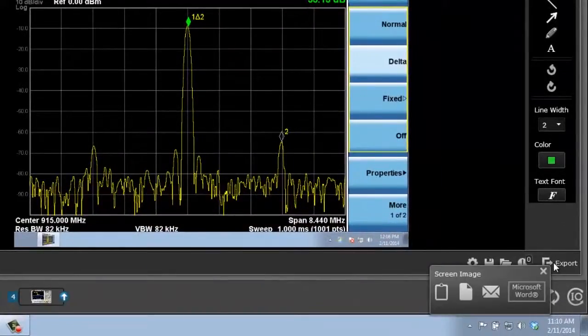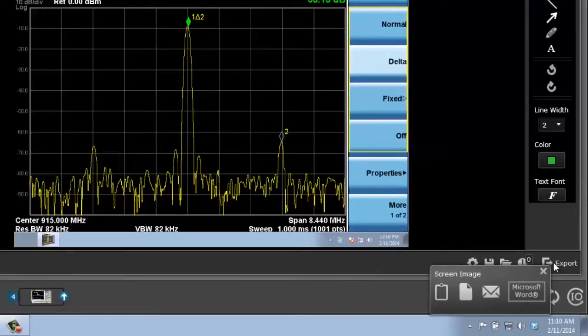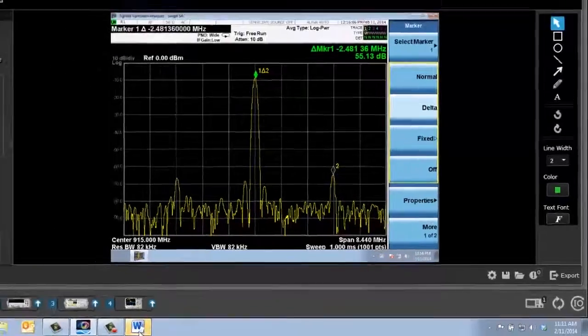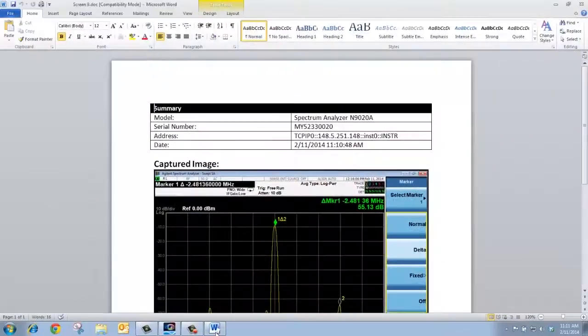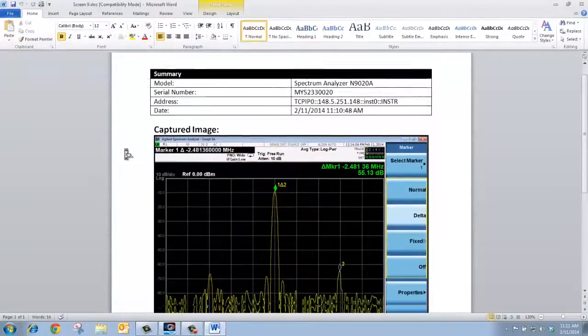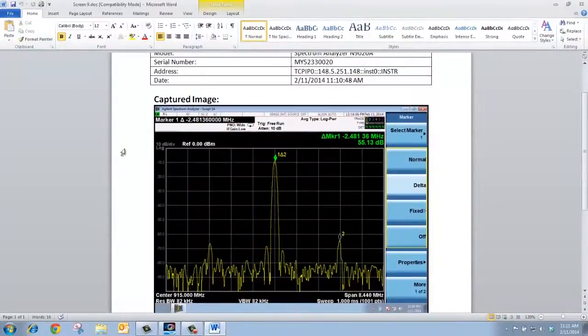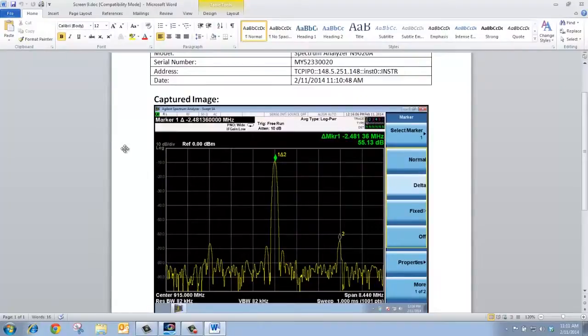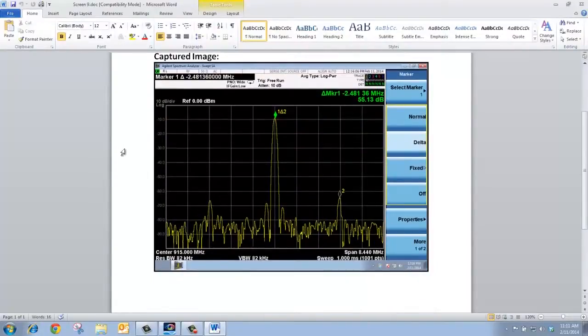I can export it as an image, or as an image attached to an email, or in a Microsoft Word document, which I'll do. Bring up my Word document, and you can see not only is the screen image captured, but also information on the instrument is also captured. So I can use this as a baseline to start writing a test report.